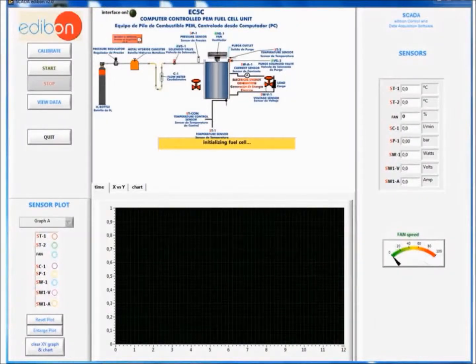Before we start using the unit, I will explain the layout of the user interface. The main controls are in the upper left corner. This includes the calibration, start, stop, view data, and quit button. A schematic diagram shows the layout of the components in the system. The sensors are located in the upper right. This includes temperature sensor for the fuel cell stack, temperature sensor for the purge flow, fan speed, flow sensor, inlet pressure sensor, power sensor, voltage sensor, and current sensor.